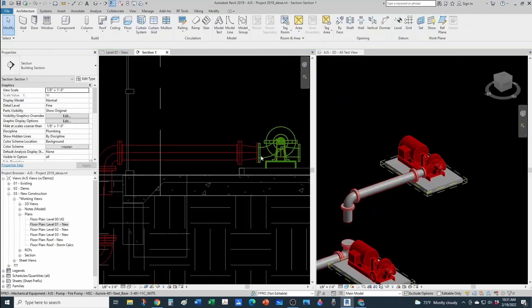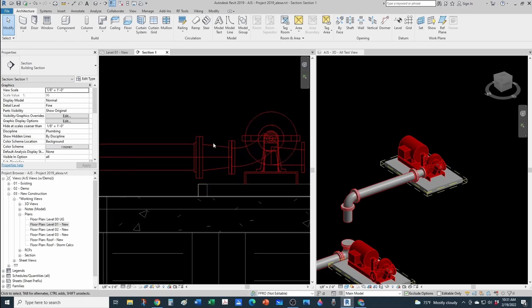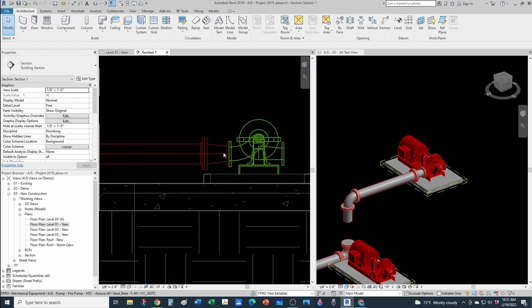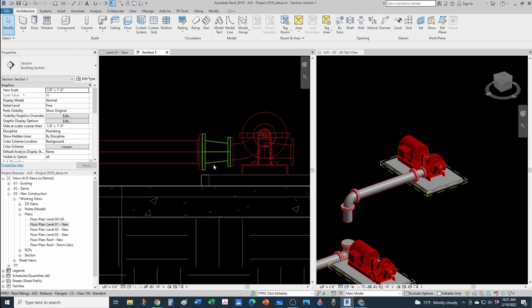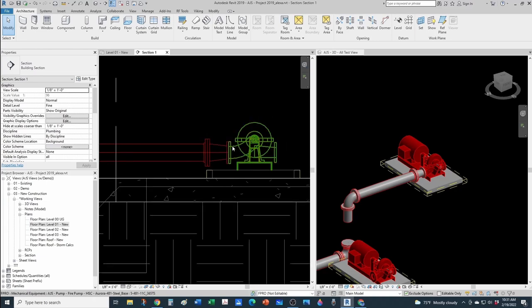But in this case, I'm just gonna take it align to my suction here. One challenge that can present to you if you're actually using an eccentric reducer is that your suction and your discharge won't be aligned. So that's why I find it so practical to just use a concentric reducer here and just call for an eccentric one.